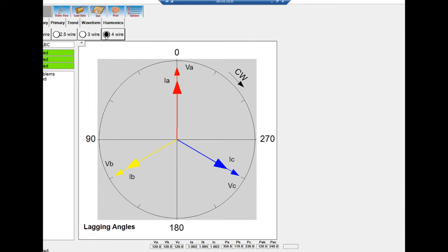And now the service, you'll see, has changed to a YABC service. It detects that automatically by the vectors being seen on all 3 phases, and determines, because I'm seeing delivered power on A, B, and C, and I've selected 4 wire, it knows it's a Y service. And it'll tell you it's a Y service. There's no problems with the service. Life's good. If I chose 3 wire, it assumes it's a delta service at that point. It brings up a delta ABC, says there's no problems because I've got a 3-phase, 3-wire delta I'm hooked up to, and this is the diagram that I would be seeing.